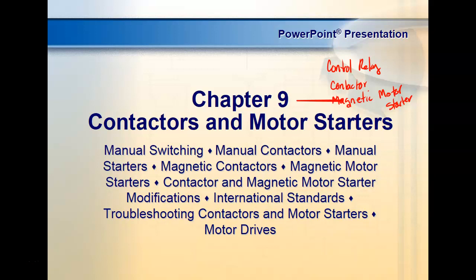A control relay, these are relays, contacts never leave the control circuit. They're never in the power circuit. They're not designed to run load. They run a solenoid, but they're not going to run load. Very seldom will you find a control circuit that high. Most of our motors are power circuits. So relays, these are relays, contacts never leave the control circuit.